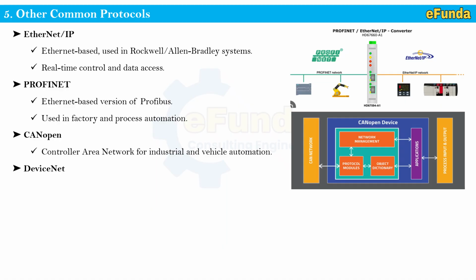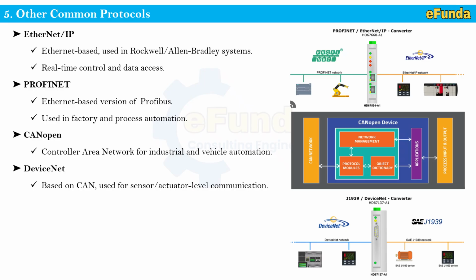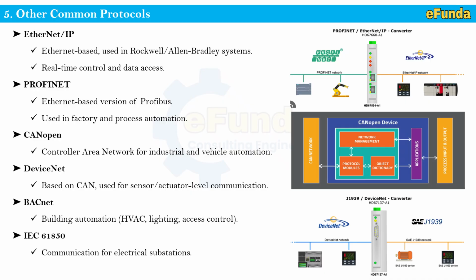DeviceNet, based on CAN, is used for sensors, actuators and device level communication. One can refer to the third picture where a DeviceNet converter is shown, with various field devices connected to DeviceNet as a communication protocol, where the DeviceNet network as well as SAE J1939 networks are used to handle the data exchange between sensors and actuators for device level communication. BACnet is for building automation, that is HVAC, lighting, access control, etc. IEC 61850 is the communication used for electrical subsystems or substations.